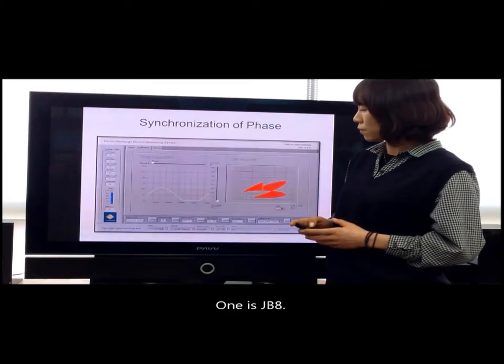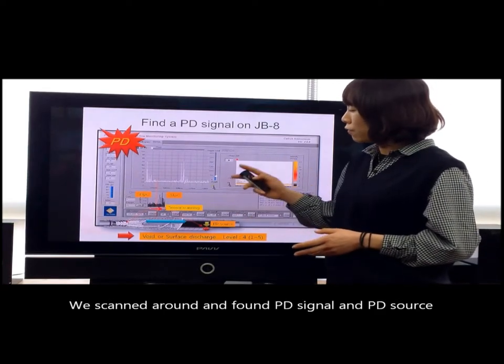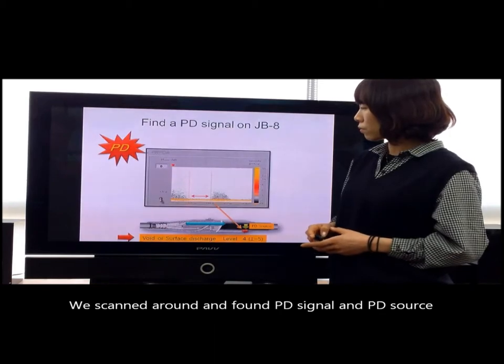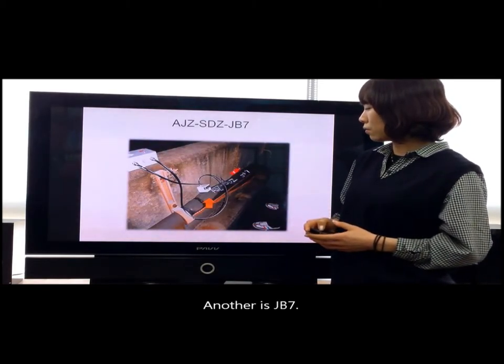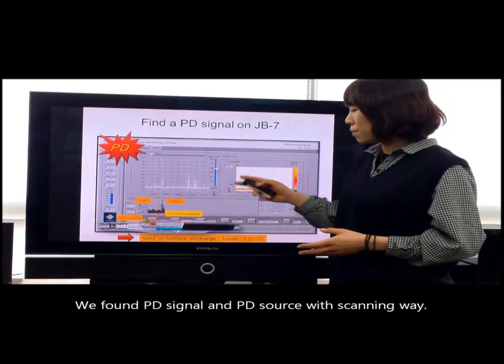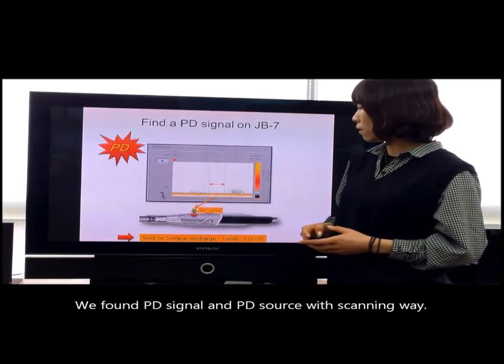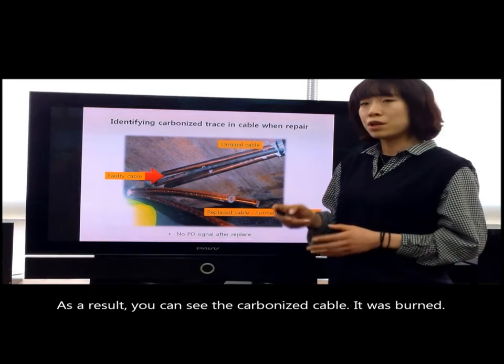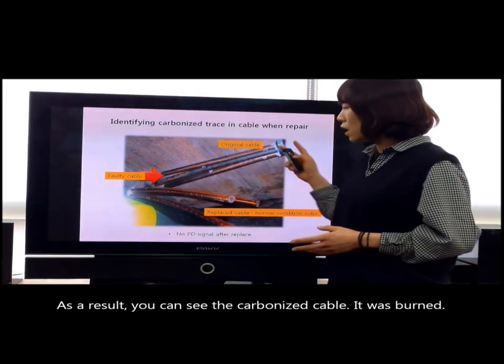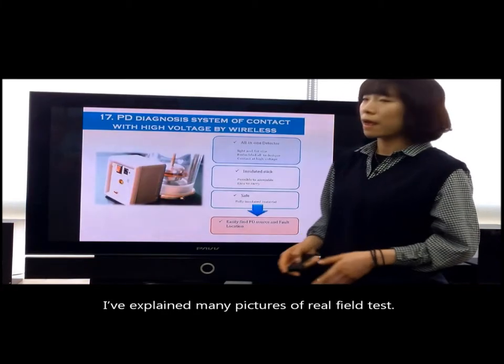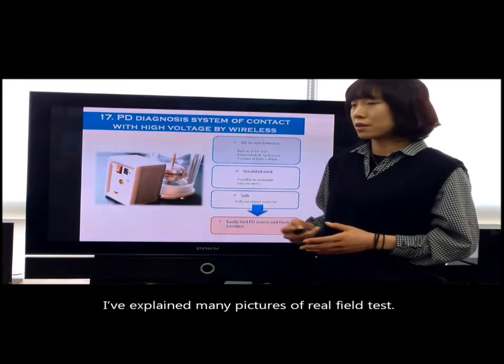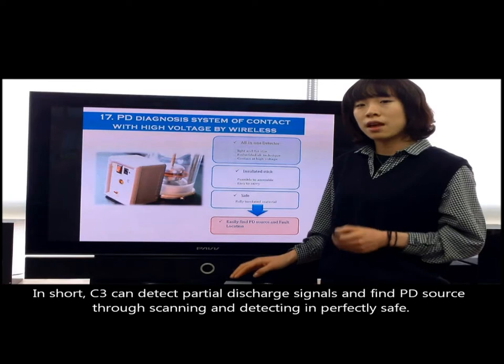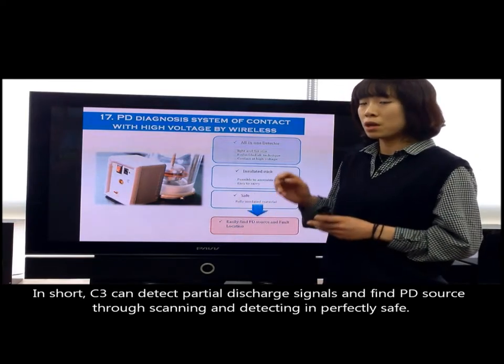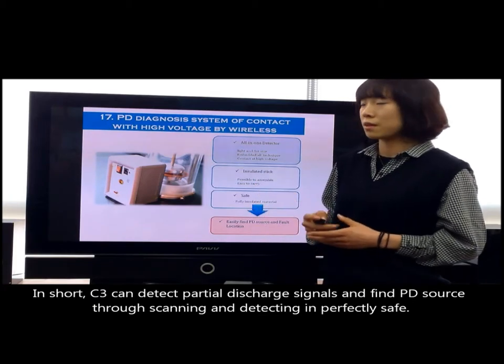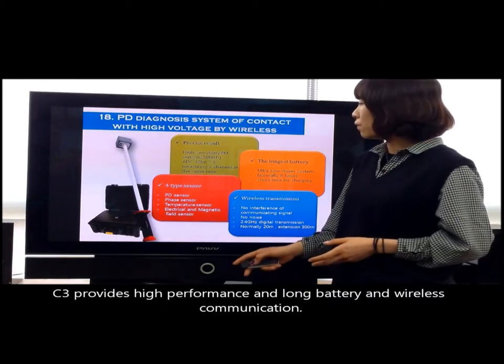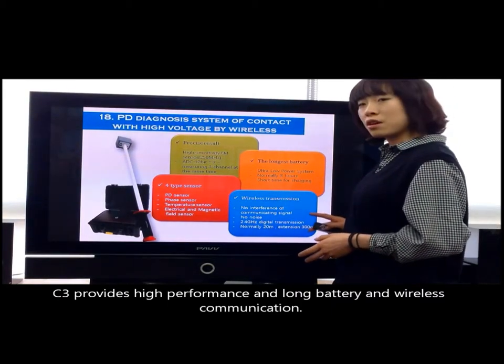One is JB8. We scanned around and found the PD signal and PD source. Another is JB7. We found the PD signal and PD source with the scanning way. As a result, you can see the carbonized cable. It was burned. I've explained many pictures of real field tests. In short, C3 can detect partial discharge signals and find the PD source through scanning and detecting, perfectly safe. C3 provides high performance, long battery and wireless communication.